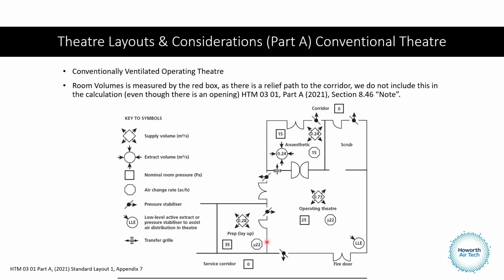If you notice these numbers in the square boxes here, this is the nominal room pressure. This is operating at 35 pascals and this is at 25 pascals. So by default, this pressure stabilizer here would be 10 pascals between the spaces. The dead corner in the operating theatre has a mechanical low level extract path, and then we have a natural relief here onto the service corridor.